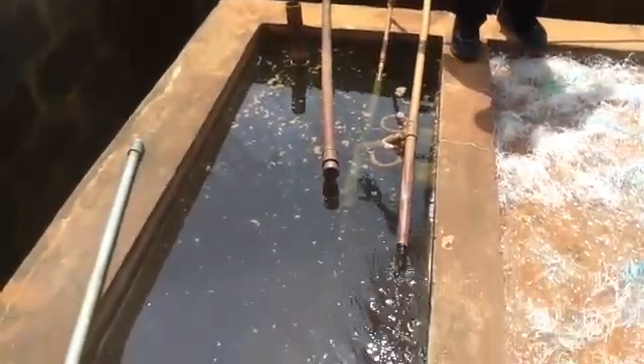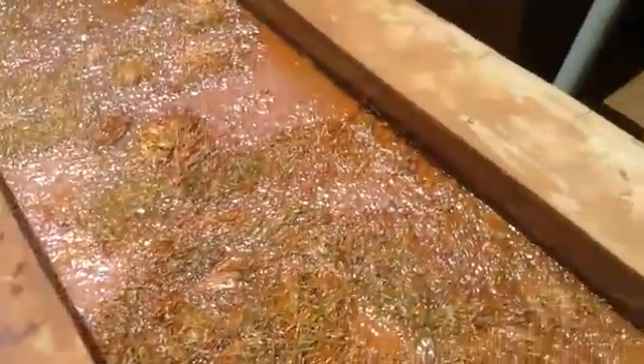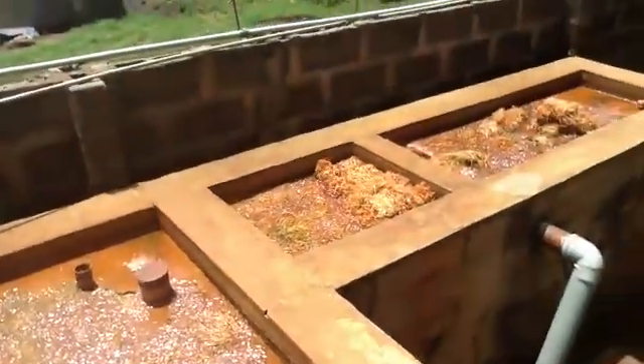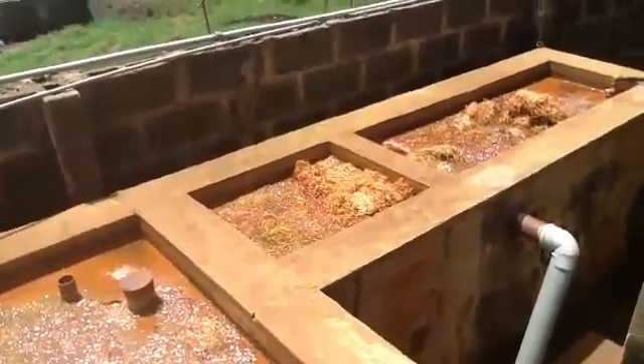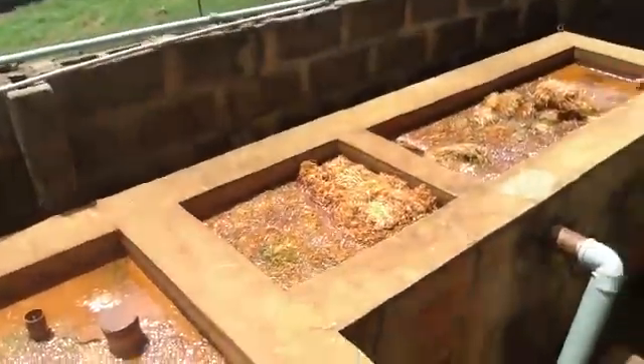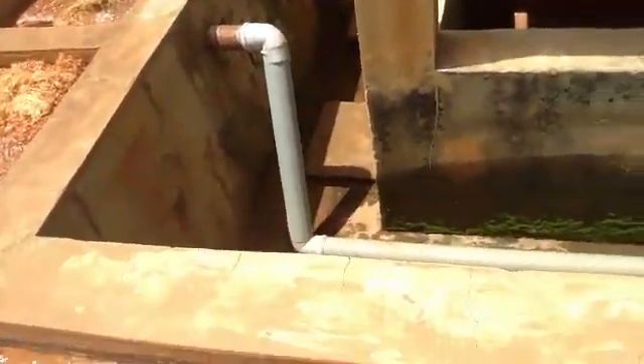Water comes in and looks crystal clear, but there indefinitely you'll still have all these shining things. You'll see how the ferric and ferrous sources are all concentrated there. It is an effort to filter, but the filtration effect is only about 70%, whereas the fish needs it at almost close to 90%. So what will happen is that this is going to be substituted with a granular media, instead of this sediment capture system, so that they can have clean water.